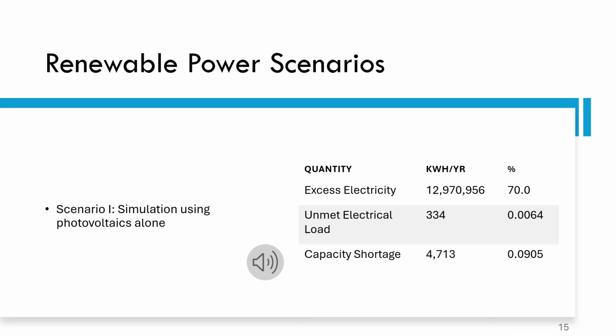We simulated 4 different scenarios. For the first scenario, we simulated using PV alone. We assumed constant load, so we set our constraints to have 100% load in current time step. We also want a reliable system for the data center, so we set 0 annual capacity shortage. The electrical simulation result shows that we have excess electricity of 12,970,956 kilowatt hour per year, which is very high. Then we had some unmet electrical load of 334 kilowatt hour per year and capacity shortage too.